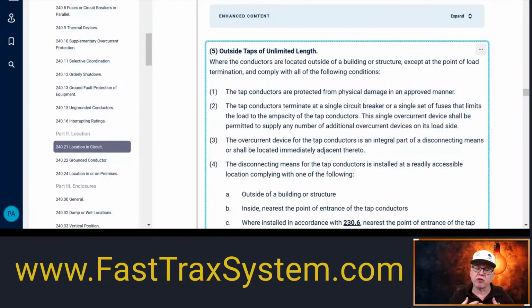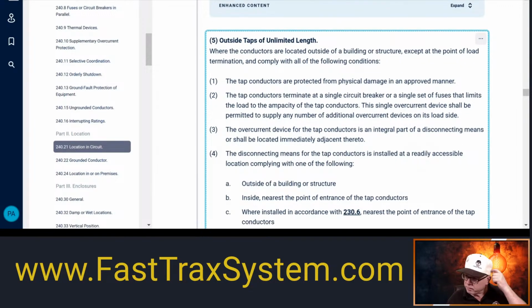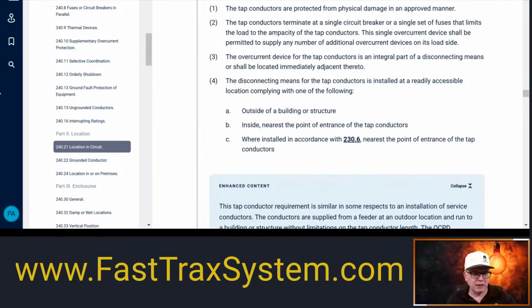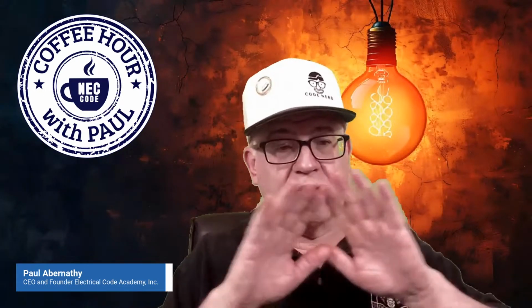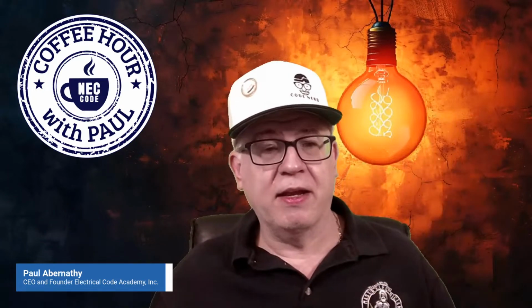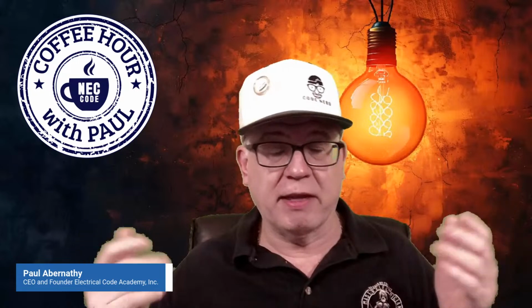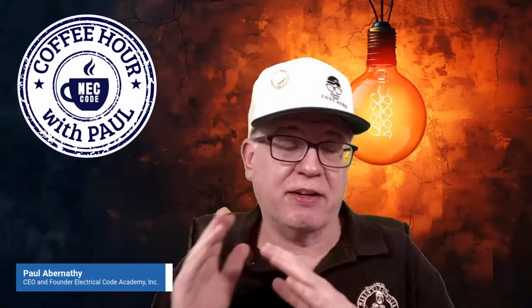Okay. Now the reason for this is because you could put that outside and then it feeds a panel directly inside, that type of scenario. So it's giving you a little leeway. It could be all in one equipment or it can be two separate, but they have to be immediately adjacent to each other. And I do get a lot of people that argue the term immediately adjacent. They're like, well, what's immediately adjacent when the code says do that? If there's room to put it right beside it, to me, that's immediately adjacent. If I have a 10-foot wall span and I want to put it 10 feet away, and I had plenty of space to put it immediately right beside the equipment, then that doesn't, to me, meet immediately adjacent. If it had said just adjacent to it, but this says immediately adjacent, so right beside it.